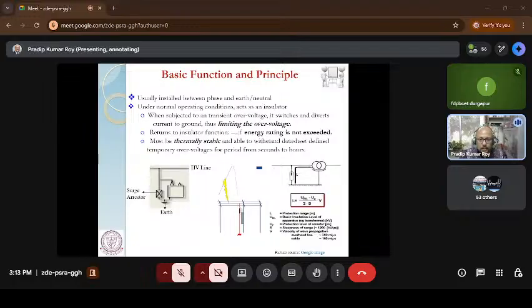So if you look at this figure, it talks about how far I should install the surge arrestor from the equipment or transformer. This is normally called the protection level, and this protection level depends on the insulation level of the equipment. Some people say the transformer was blasted. Blasting is nothing but the insulation level of that equipment actually vanishing. Now it has become a conductor. Based on that insulation level, there are a few parameters which are based on the standard. This is actually constant also. So through this formula, we can work out how far I can place the surge arrestor from the transformer to protect it from the surge.